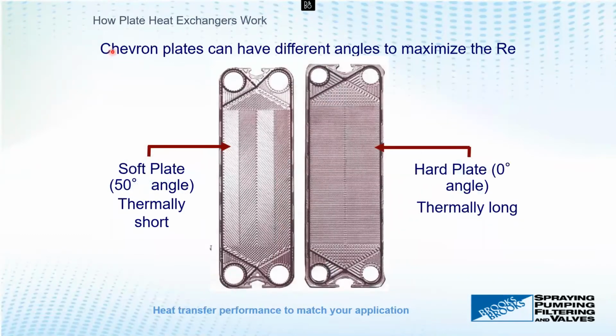Let's talk about those chevrons, or corrugations. They're designed based on the plates, the fluids, and the thickness of the plates, and they can vary—as much as 60 degrees, 50, 40, 30, down to 0. They're custom designed into your heat exchanger so we can maximize the differential pressure, the Reynolds number, and get all that nice turbulence to extract as much heat as possible.